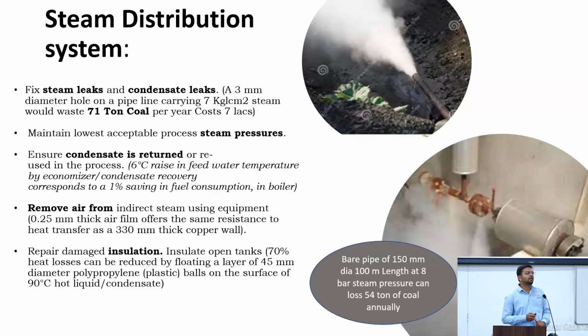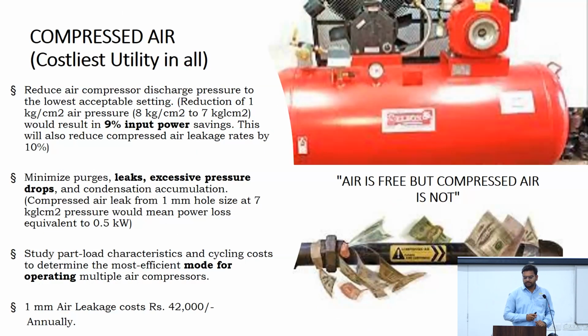As well as this, the compressed air system. The compressed air system is the costliest utility that we are using. It is costlier than the steam system also, because if we consider the cost, it is almost higher than all the other utilities, depending upon the requirement. So regarding compressed air leakage, air is free but compressed air is not. So we need to monitor the leakages also.